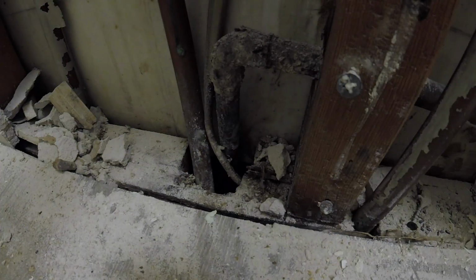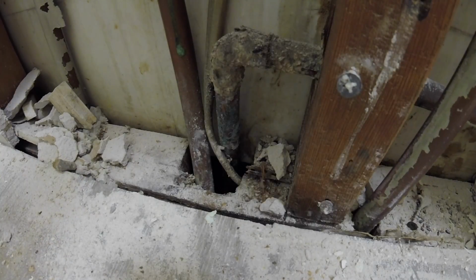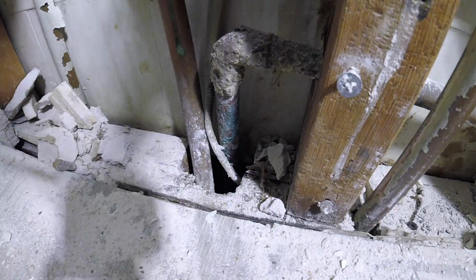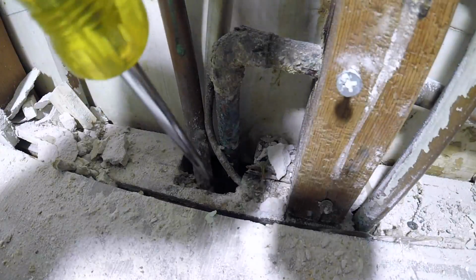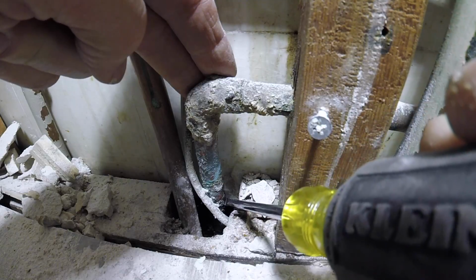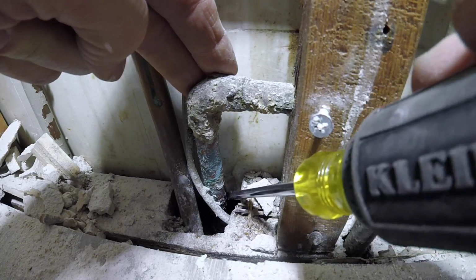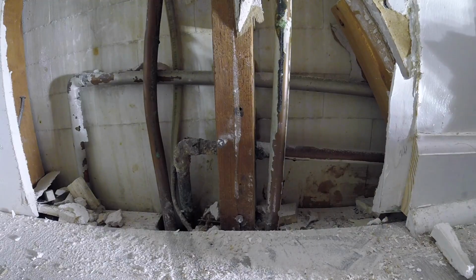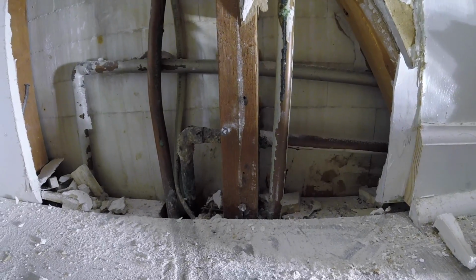Let me get my pointer for the people. Nice. Okay, where's your pointer? Here, you hold the light. Yes, I got the light. Come right over my head. I want to see down here. Oh, there it is. Other side, Bill. It's squirting against the tile right there, end of the screwdriver. Cause a leak in the copper. We're going to cut it right here and down in the heater room. So now we got to shut the building off.